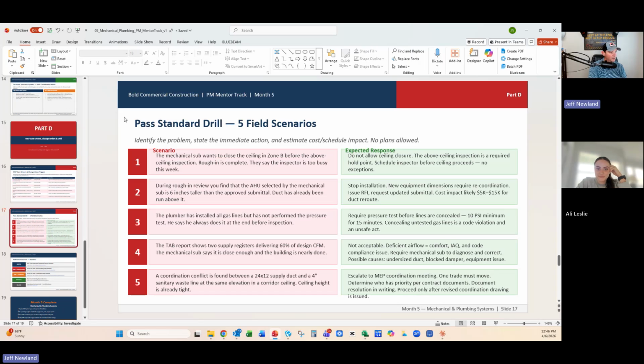During rough-in review, you find that the AHU, which is the air handling unit, selected by the mechanical sub is 6 inches taller than the approved submittal. Ductwork has already been run above it. So what would you do? We're in the rough-in stage, pretty simple, I think. Ductwork has already been run above it, so it can't be any taller.